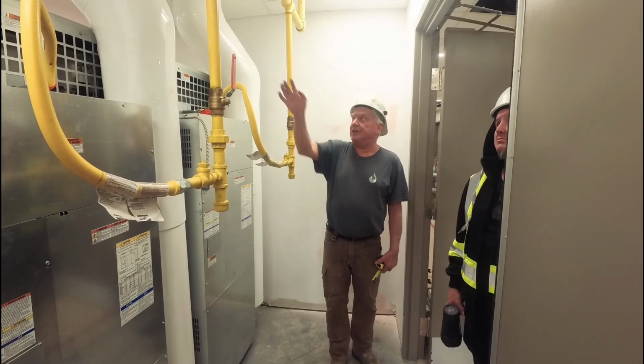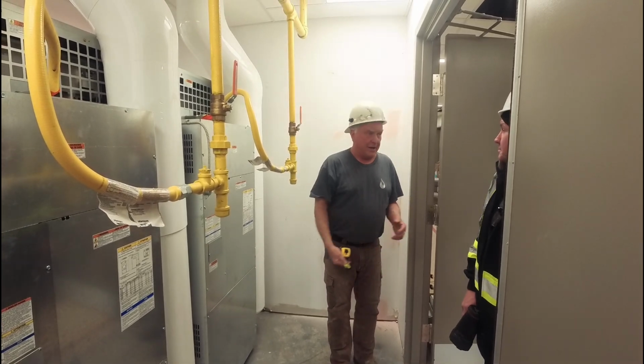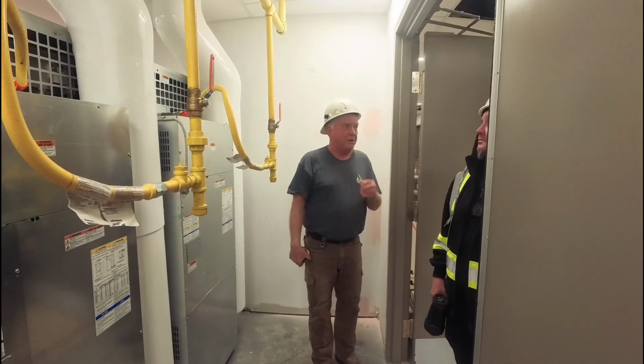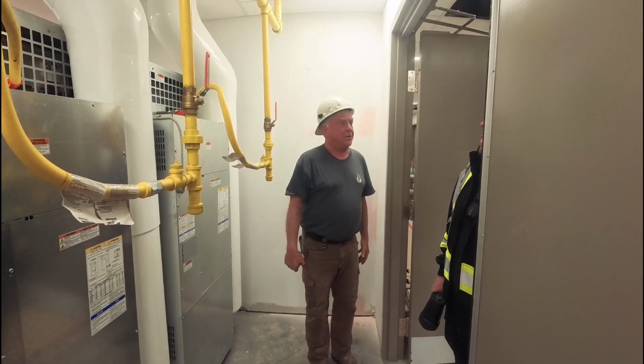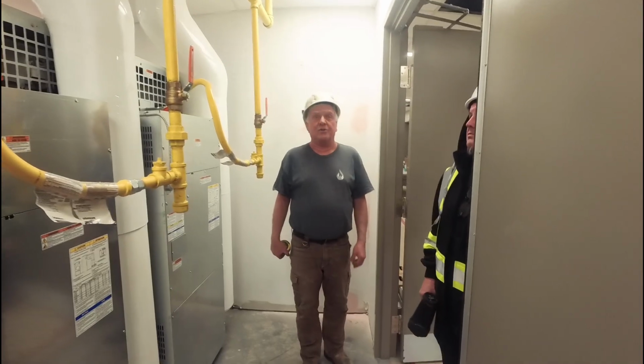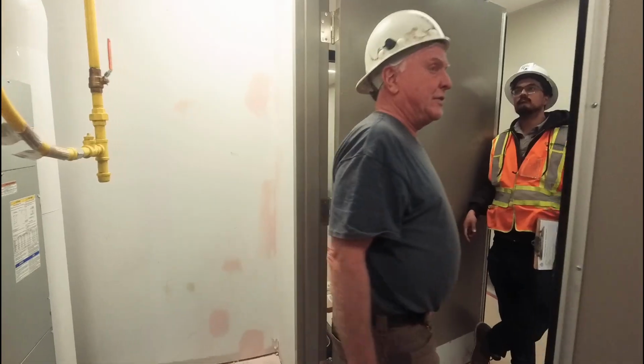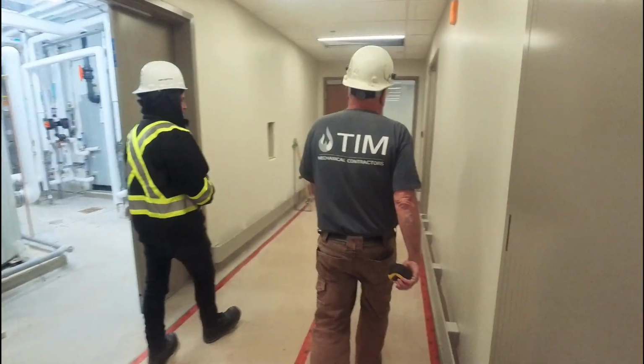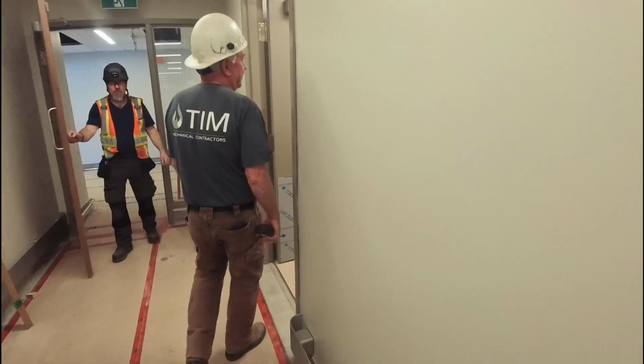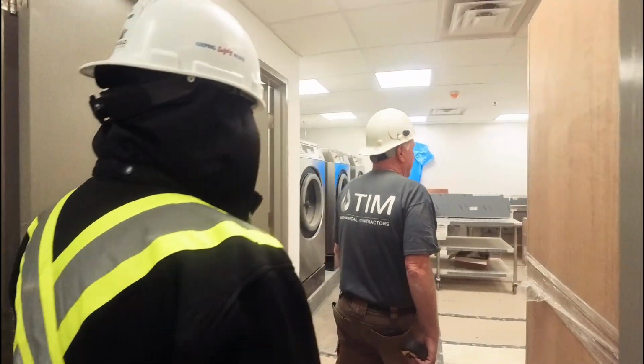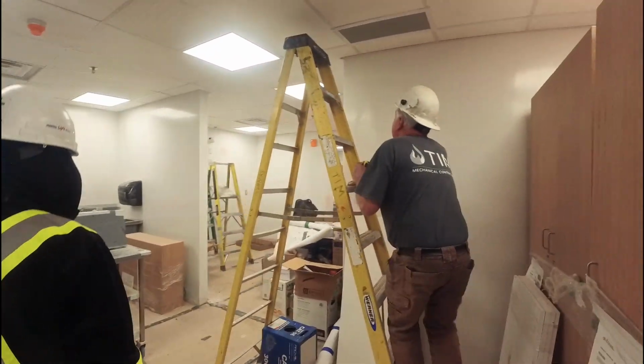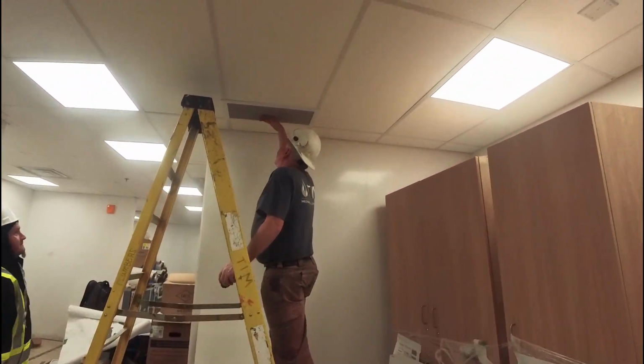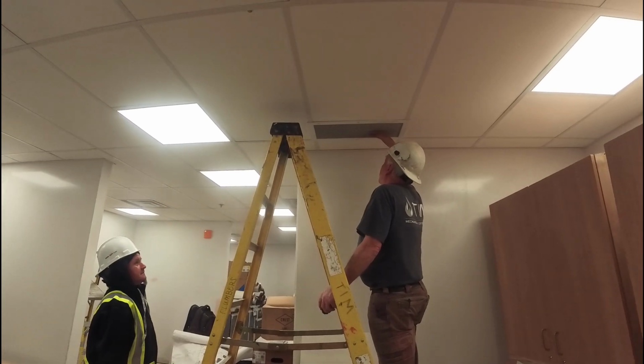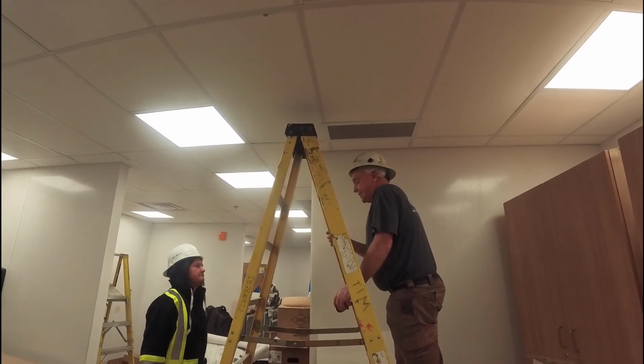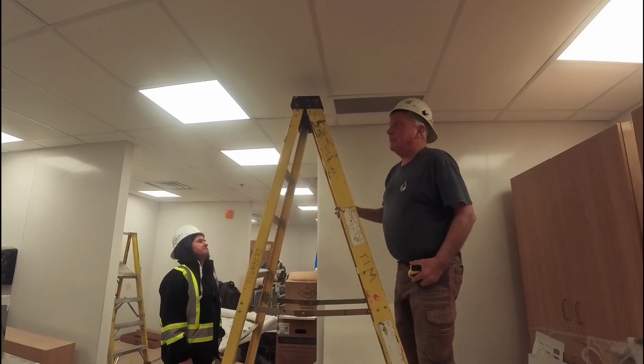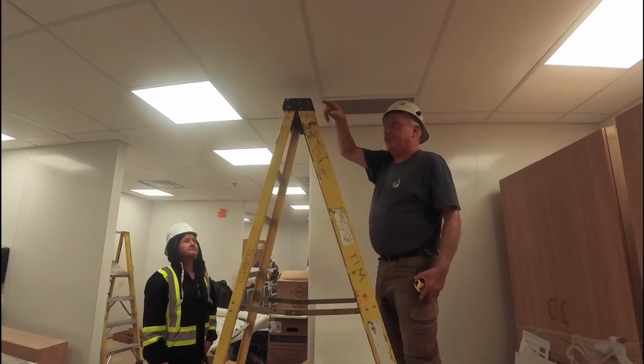Cool. This area is actually fed by another separate HVAC unit, HVAC #2, which has its own set of diffusers and returns. It was balanced yesterday, so I'll take a walk through there. I'd kind of like to hear if it sounds like the returns are tight enough for me. I'm very picky on the returns. You gotta have a balanced property, right? Well, I can live with that. It was running at 100% on the fan on the return side the other day, and it sounded awful in here. They've got it turned down adequately. He took all the readings.